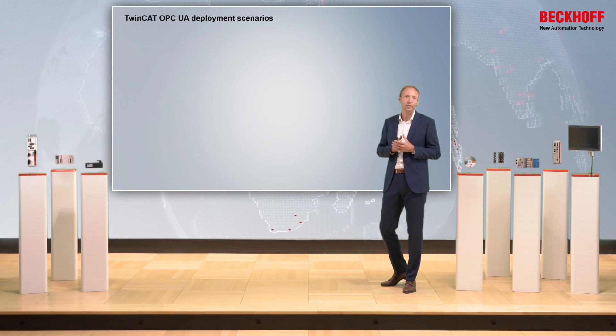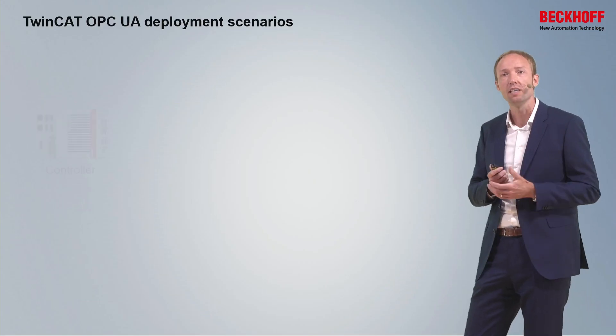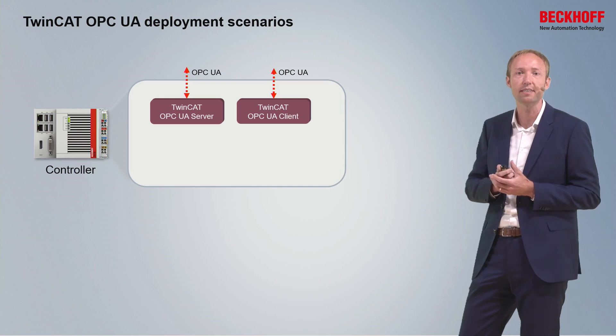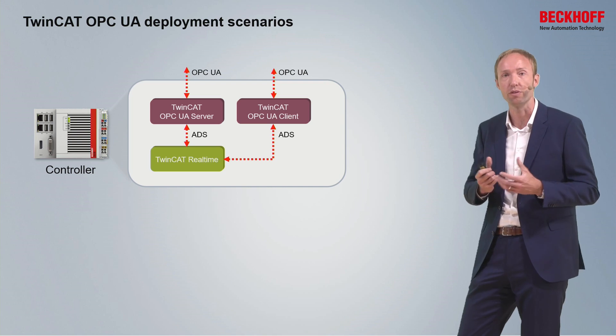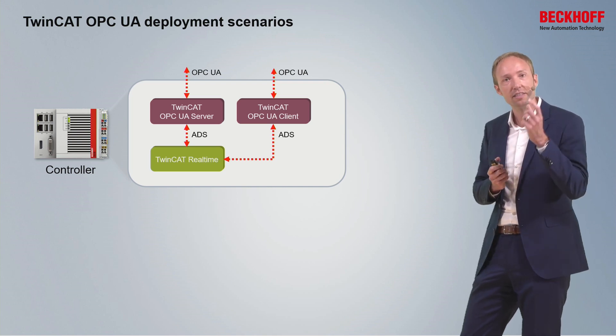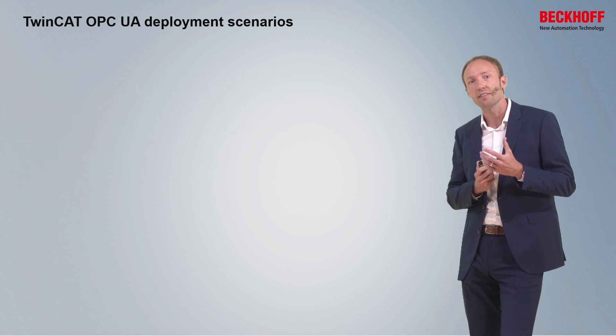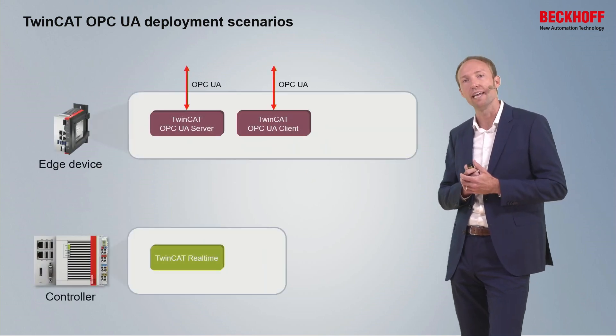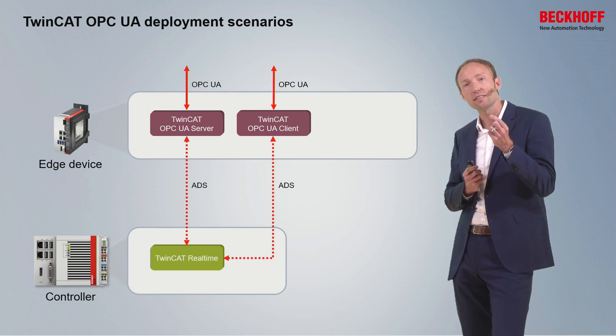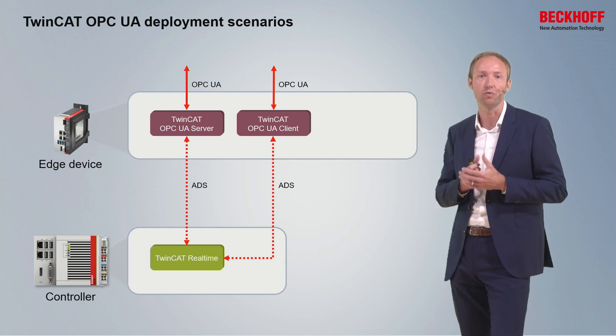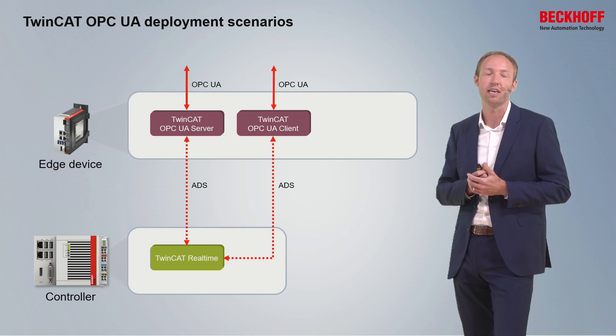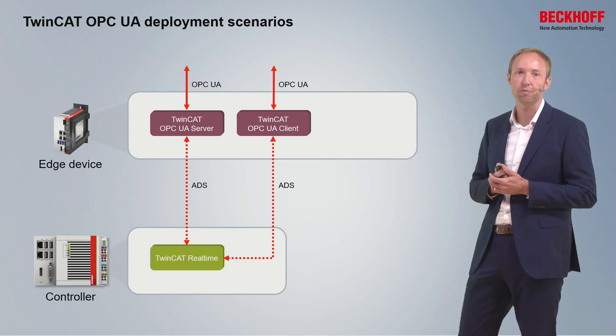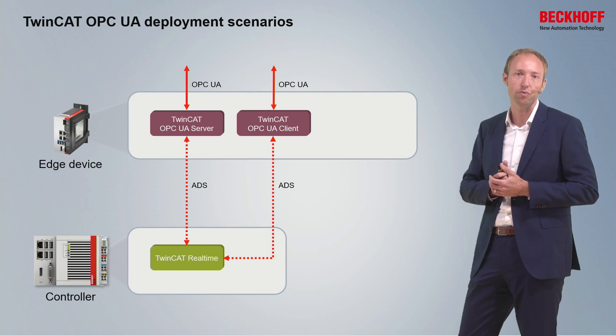In a typical deployment scenario, you install the client or server application directly on the controller — no separate hardware required. Access to the TwinCAT Realtime is done via the ADS protocol, which is capable of being routed through the TCP/IP network. In a second scenario, the TwinCAT OPC UA client and server application can be installed on an edge device, while the underlying controller executes the TwinCAT Realtime. This also enables retrofitting existing machines in a brownfield scenario.